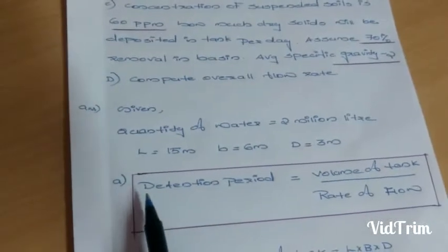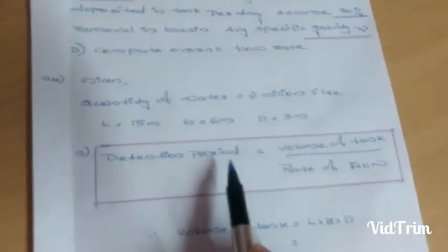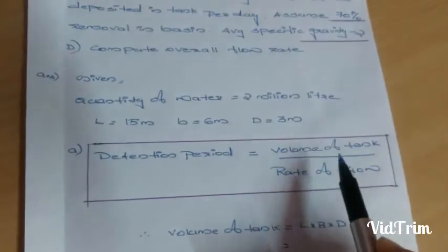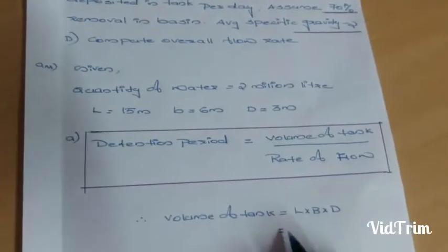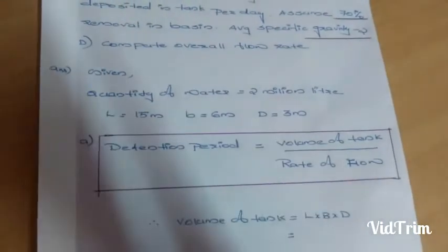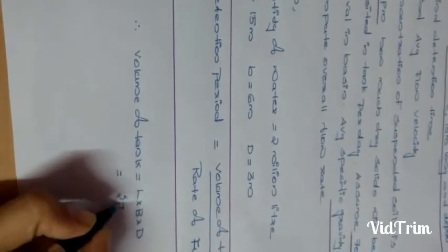First we have to find out the detention period, which is volume of the tank divided by the rate of flow. Volume of the tank is length into breadth into depth. We have length equal to 15 meter, 6 meter, into 3 meter. Multiplying this, we get volume equal to 270 meter cube.